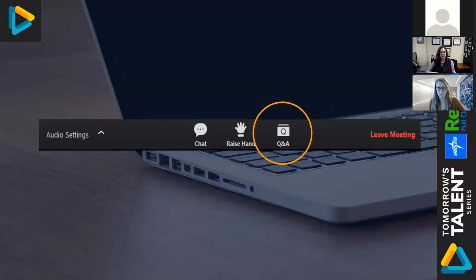So moving on to what happens to the device when you get it and it's repurposed. What are some of the tests that those devices undergo to get approval to be sent back to hospitals? There's a lot of testing that we do. Any medical device that's going to market, whether it's a new device from an original manufacturer or a reprocessed device, has to go through a series of tests, and those are defined by the FDA and ISO. So we follow the same set of guidelines the original manufacturers do. A couple of examples of the areas that we're testing: electrical safety, biocompatibility, and cleanliness of those devices.